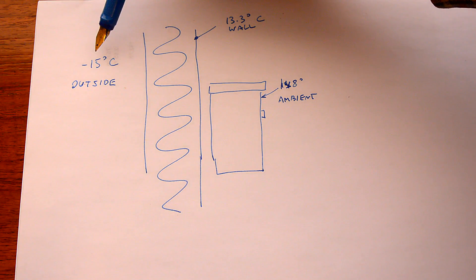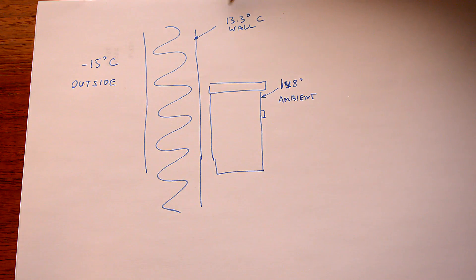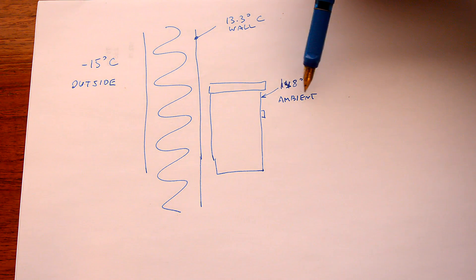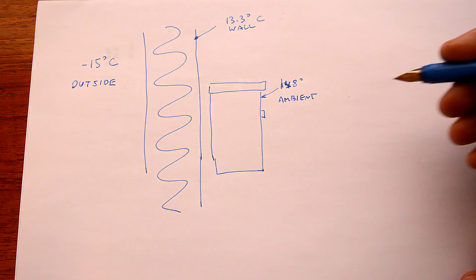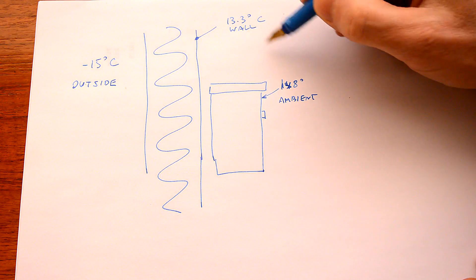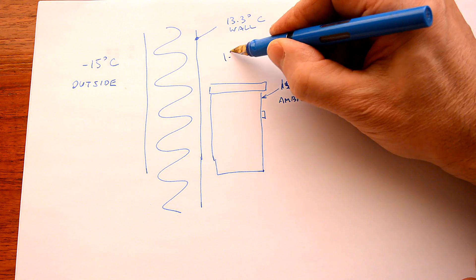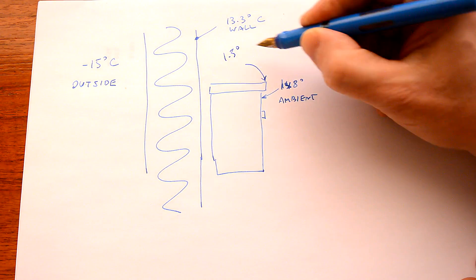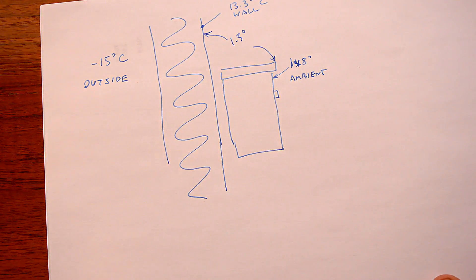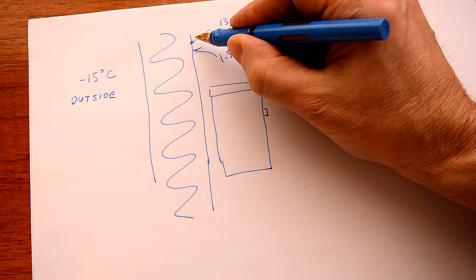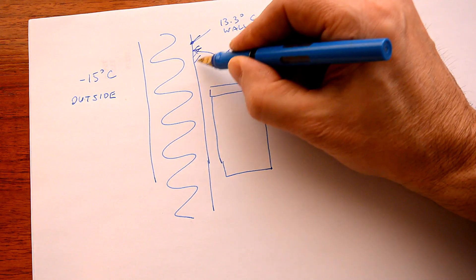The outside temperature is minus 15. So we have minus 15 outside, 13.3 at the surface of the wall, and the dresser is at 14.8 which is the ambient temperature of the room. So the wall is 1.5 degrees between the ambient and the wall surface. And at the actual surface of the wall, there's a boundary layer here.